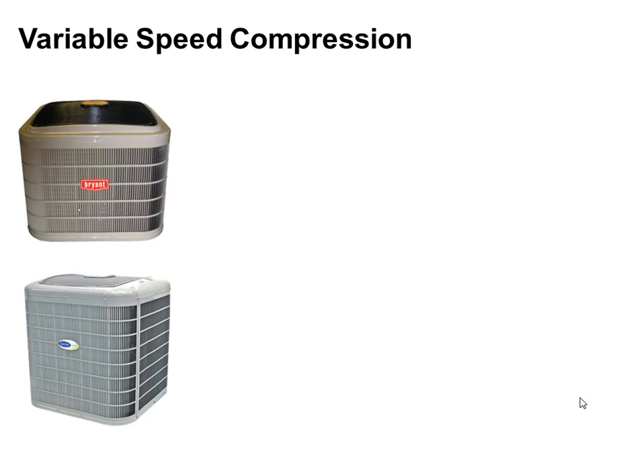In terms of these new units that we have and how they're different than regular heat pumps, because heat pumps have been around for whatever, 40, 50 years, something like that. The main big difference here is that these guys are variable speed. They have inverter compressor technology. Now, inverter compressor technology is not new to the industry. We've been doing that on duct-free splits for several years now.